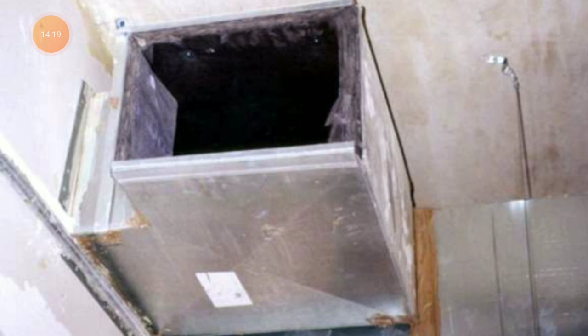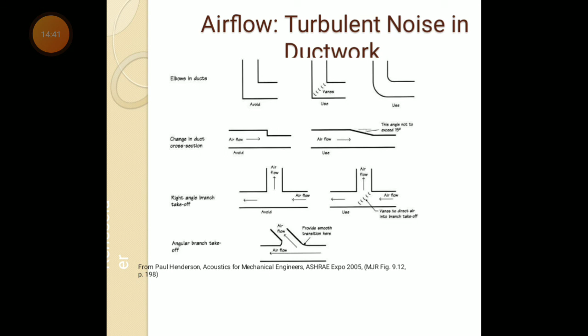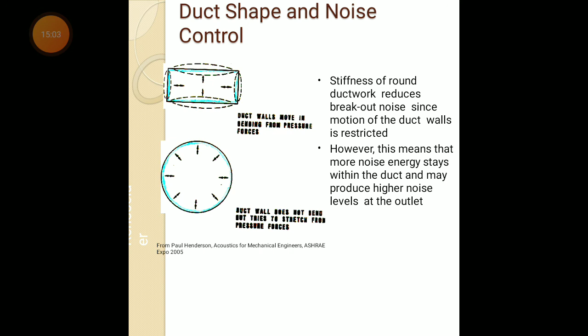When the flow of air becomes turbulent, a tremendous amount of noise is generated. So in order to reduce turbulence, some different duct work is shown here. This is the duct shape and noise control. Stiffness of round duct work reduces breakout noise since the motion of the duct wall is restricted. However, this means that more noise energy stays within the duct and may produce a higher noise level at the outlet.